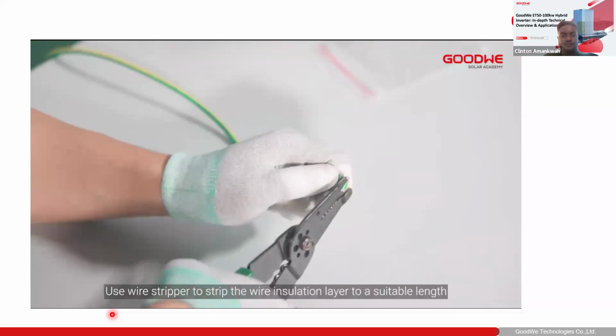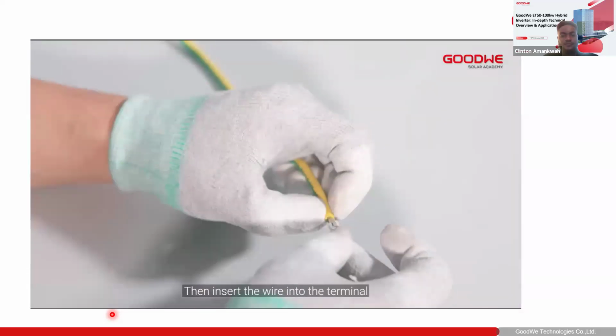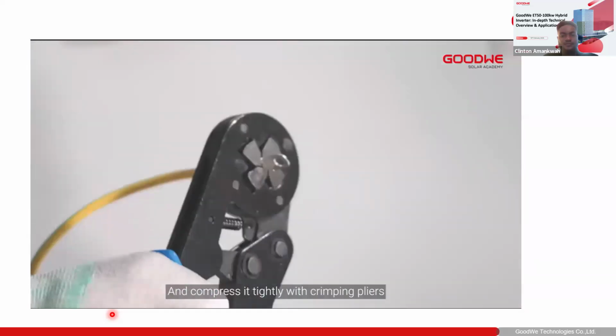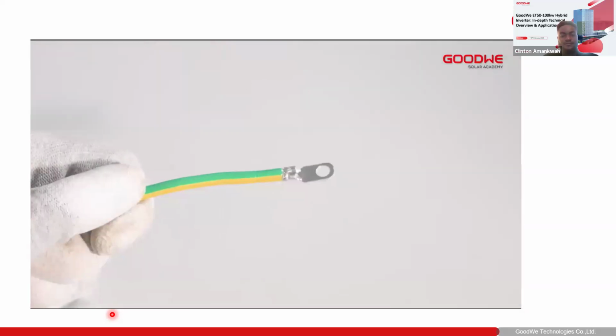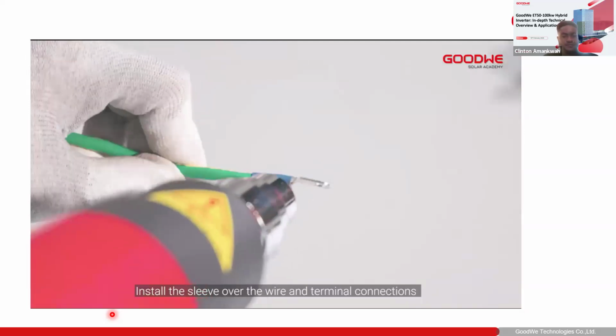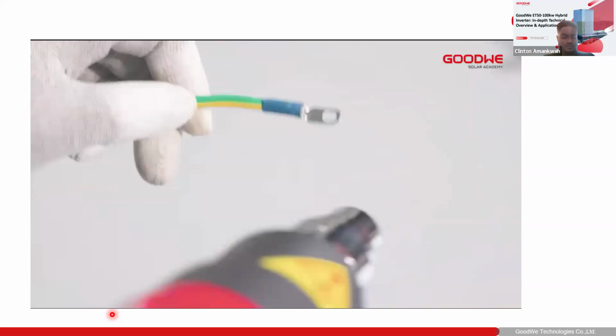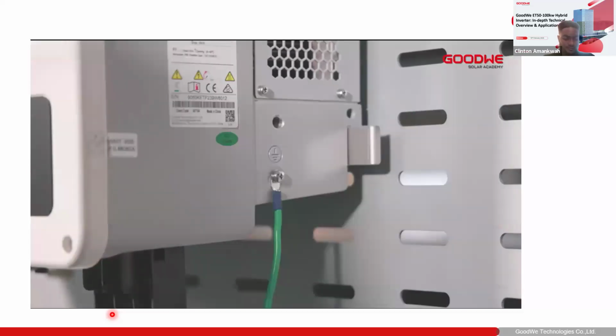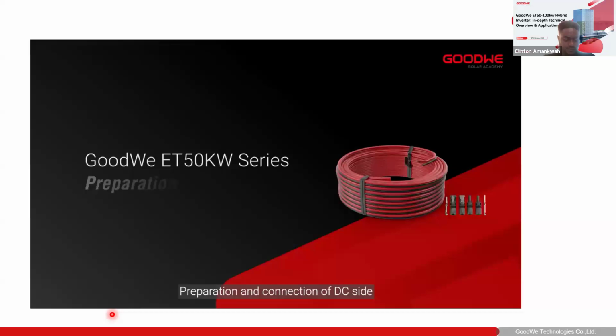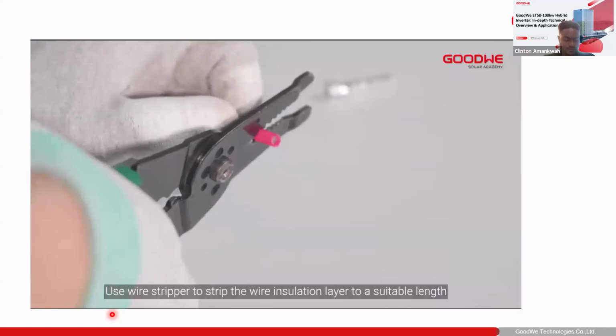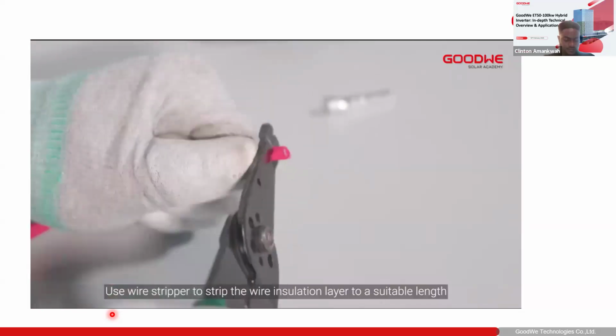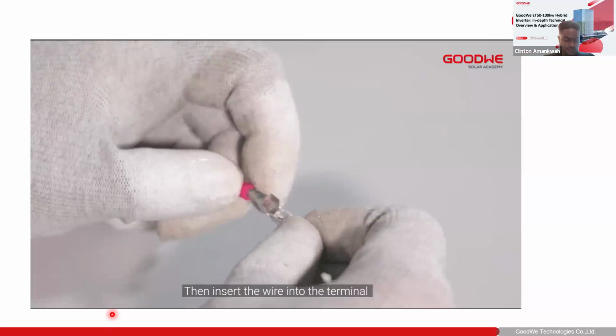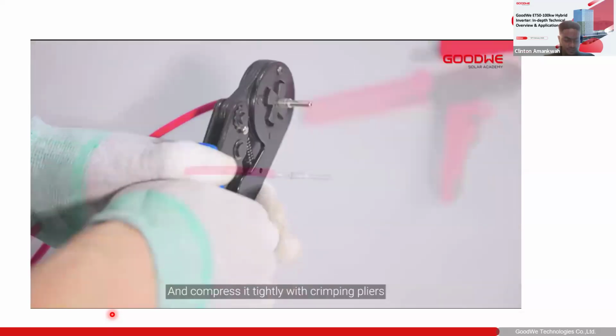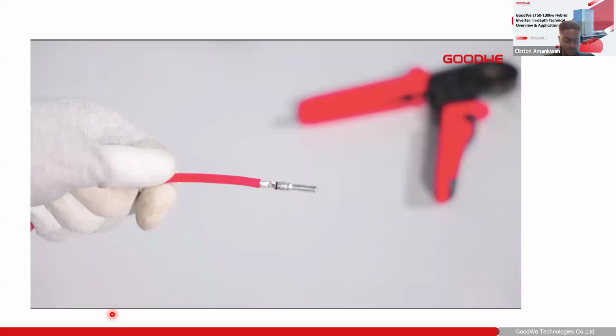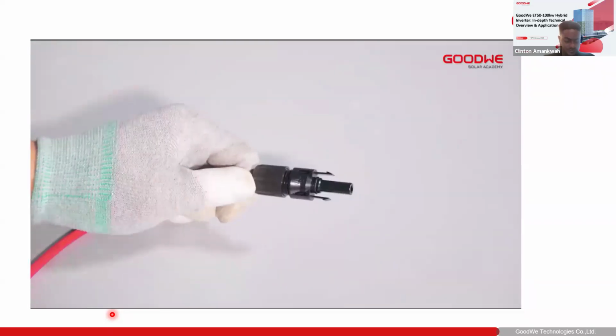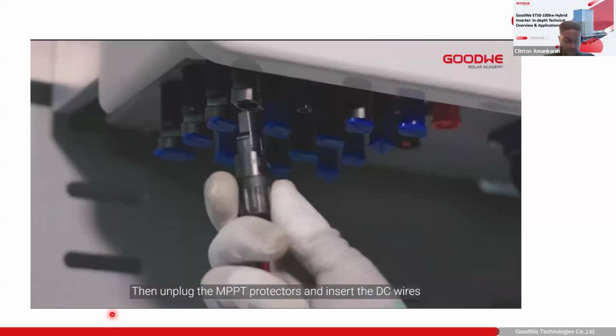Use wire stripper to strip the wire insulation layer to a suitable length. Then insert the wire into the terminal and compress it tightly with crimping pliers. Install the sleeve over the wire and terminal connections and blow it tight with a heat gun. And fix the ground cable on the inverter. Preparation and connection of DC side. Use wire stripper to strip the wire insulation layer to a suitable length. Then insert the wire into the terminal and compress it tightly with crimping pliers. Insert the wire into the positive DC connector. Then unplug the MPPT protectors and insert the DC wires.